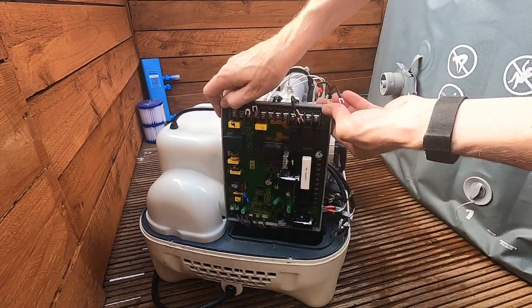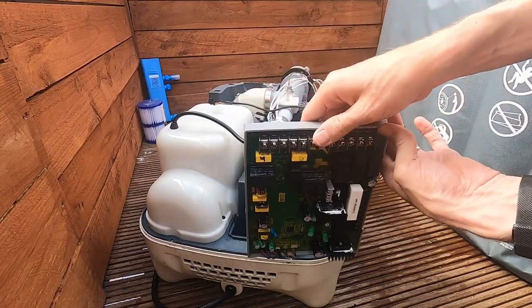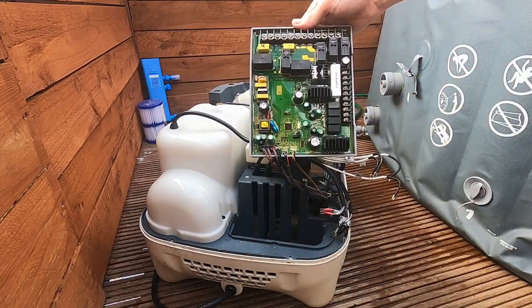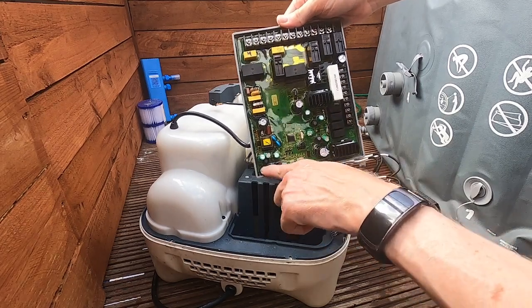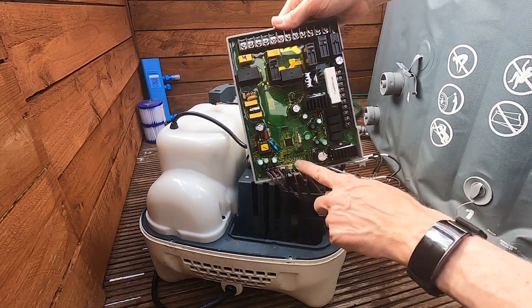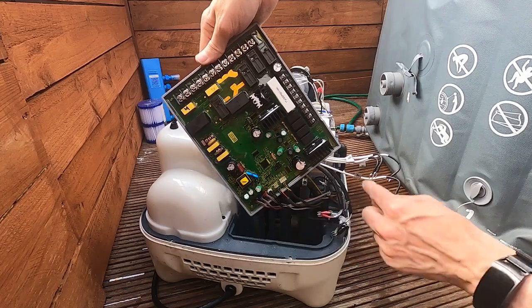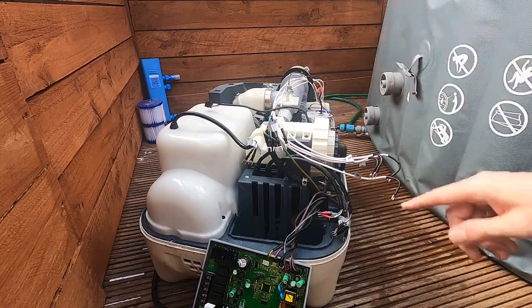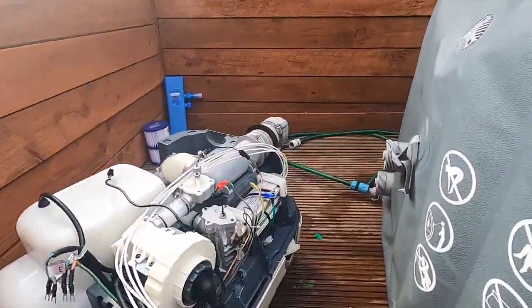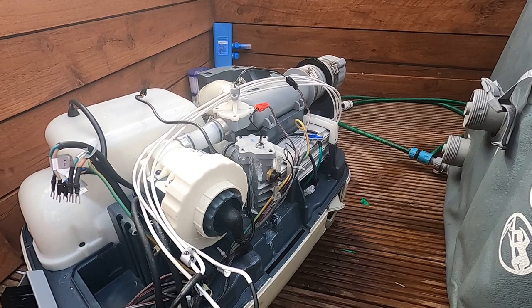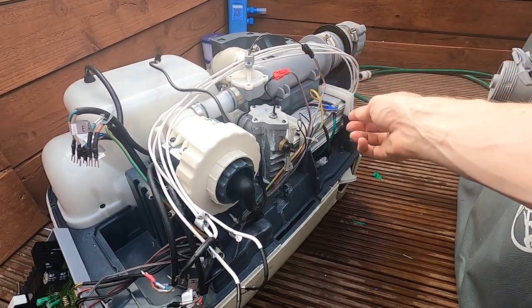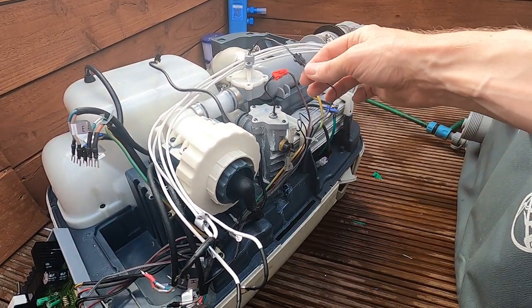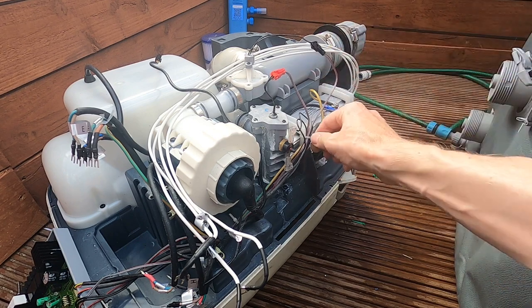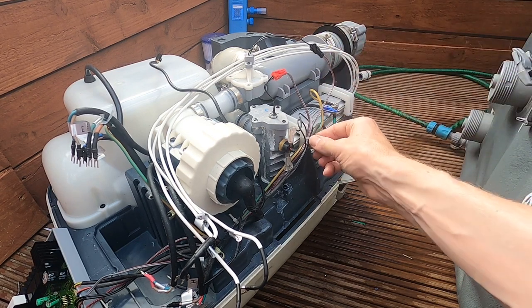So we can now take our main processor board up. You'll see there's another bunch of connectors along the bottom, and these are potted in, glued in, so you can't remove them, but they connect to the various temperature sensors and they all have small connectors on them. If we follow the wiring back, you can see those connectors for things like the temperature sensor, the cutout, and the flow sensor. You might find there's a few cable ties and things like that which we need to cut, and then we can take the board away.